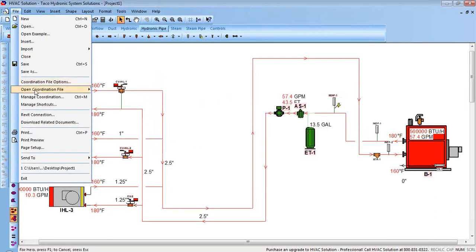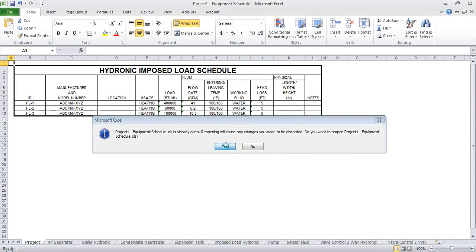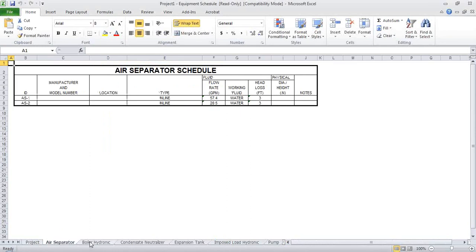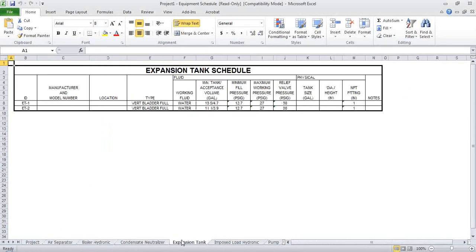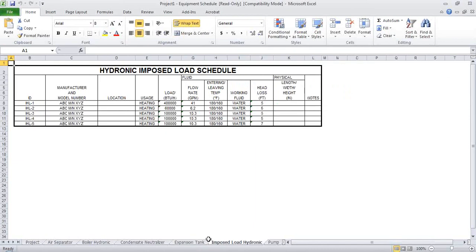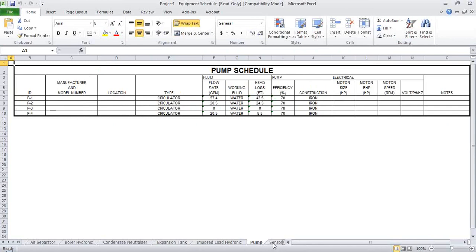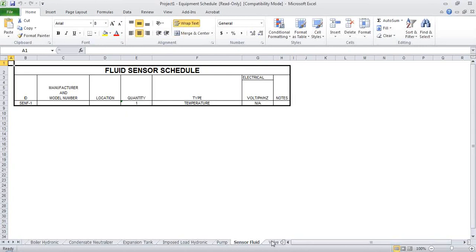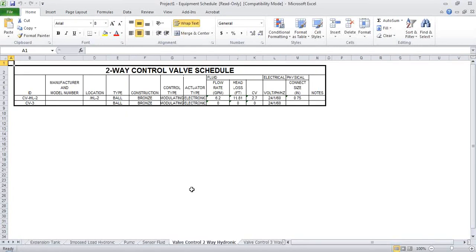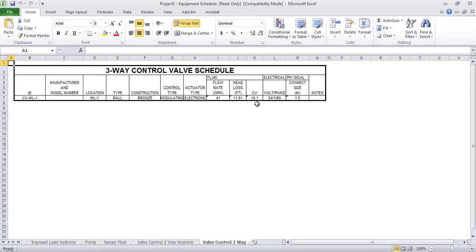If I go look at the equipment schedule now, I have multiple air separators and boilers on my drawing, multiple neutralizers, two expansion tanks, more fan coils, and more pumps. I also have new tabs — one for the temperature sensor I added, one for two-way valves and three-way valves. It defaults valves to modulating, but you can manually change them to two-position. The schedule does give you the CV of the control valve so you can properly select it — if you know the head loss and flow rate, it calculates CV for you.